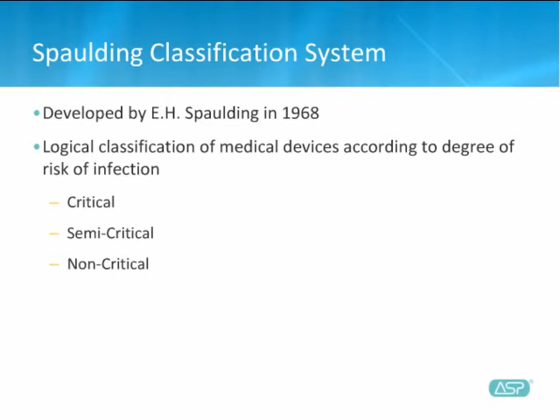As you all know, we still use the Spaulding system of classification today. Critical instruments enter sterile tissue or body cavities, break mucosal barrier, and/or enter the vascular system. Examples include choledocoscopes, biopsy forceps, and angioscopes. Semi-critical instrumentation comes into contact with mucous membranes or non-intact skin and is commonly cleaned with high-level disinfection. Examples include endoscopes, laryngoscope blades, and respiratory equipment. Non-critical instrumentation comes into contact with intact skin, but not with mucous membrane, and low-level disinfection is used. Examples include bedpans, stethoscopes, and blood pressure cuffs.